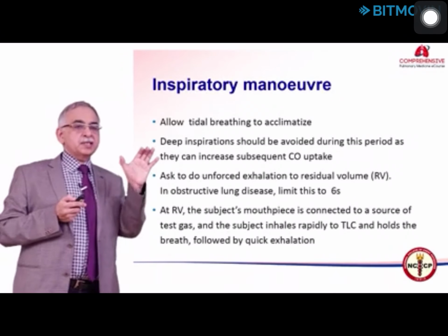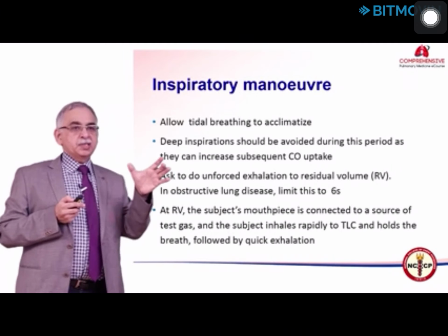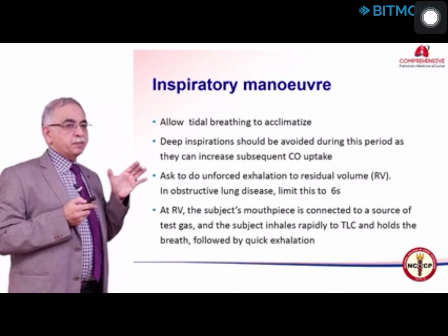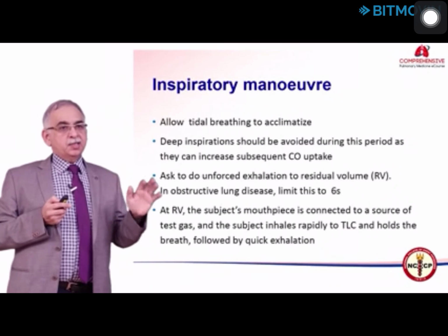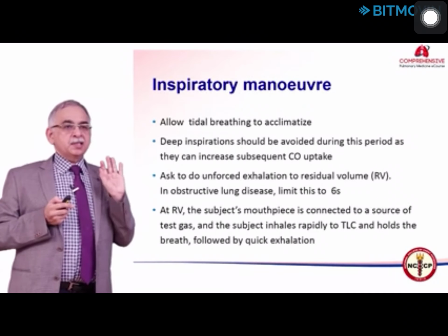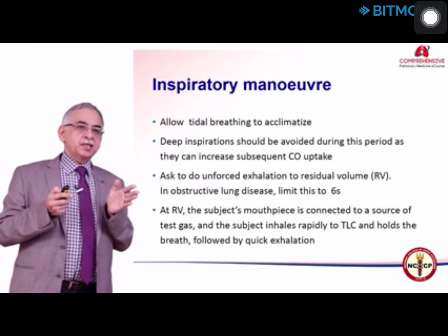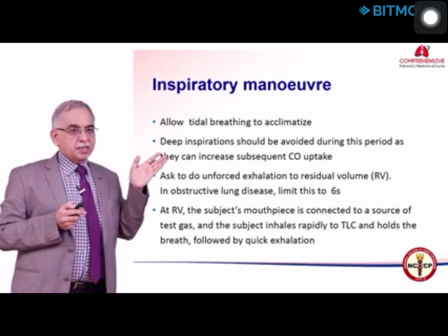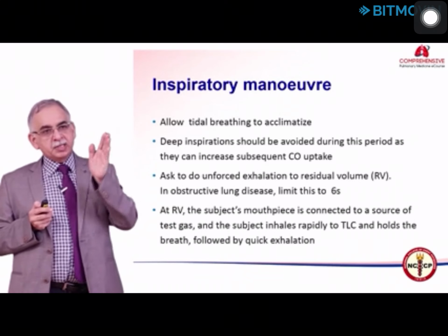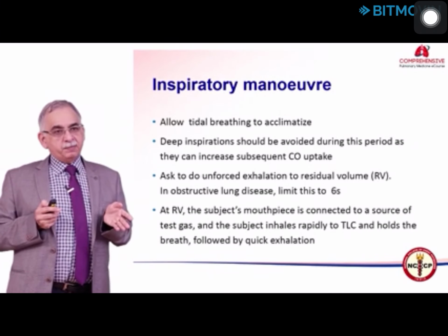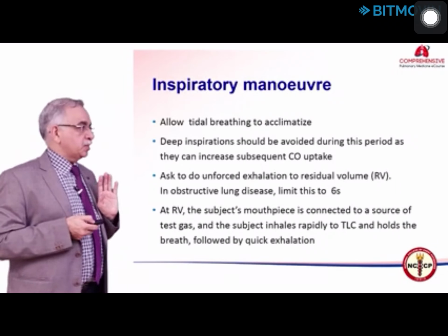This breath holding is set in the equipment. There is a shutter which drops and the patient is asked to relax. The shutter remains closed for about 9 seconds. After that, we ask the person to breathe out fully and collect the air which is coming out. It is a very simple and quick procedure in sequence: tidal breathing, breathing out to residual volume, take in a deep inspiration, hold breath and then breathe out. So, expiration, full inspiration, breath holding and expiration. These are the steps required in the maneuver.